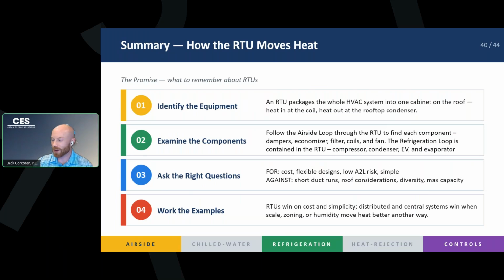What do we want to remember about these rooftop units? We want to be able to identify the equipment, right? The whole unit sits on the roof. The airside loop and the refrigeration loop are combined, and the components that make up each one of them, you just got to follow your airflow through the unit, and your refrigeration loop is all contained in the rooftop unit too. They're plug and play, right? All of these components can be added flexibly to meet the demands of your space. Add a heating coil, add a reheat coil, take away the heating, add in an extra fan, you name it, your rooftop units can be flexible enough to handle it.